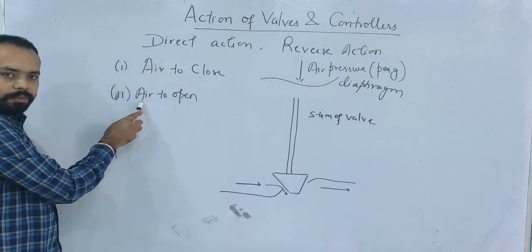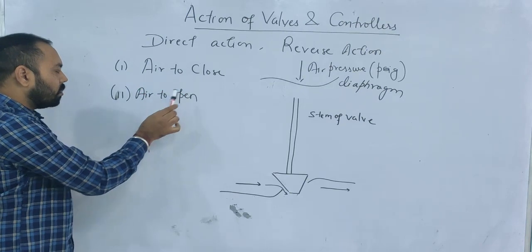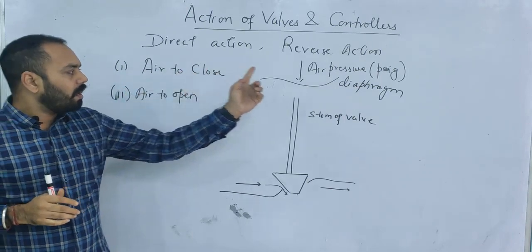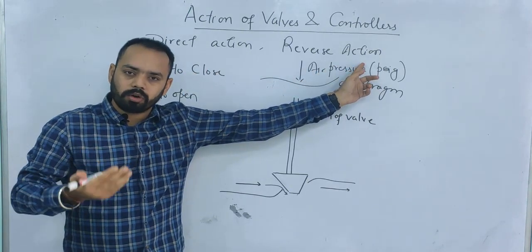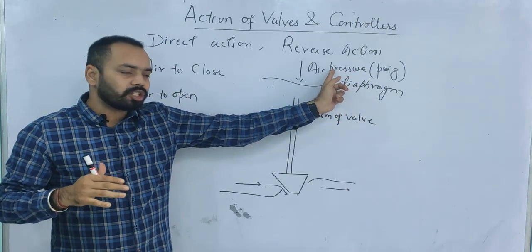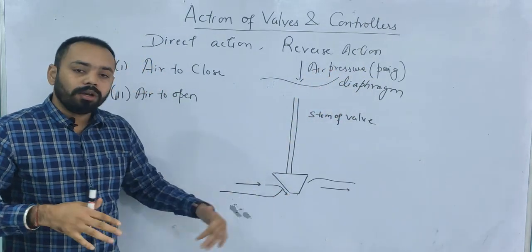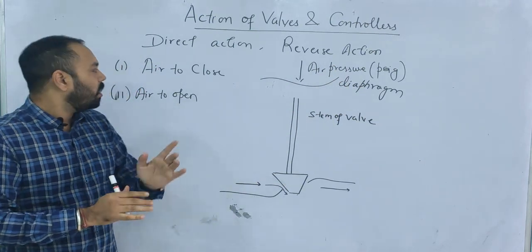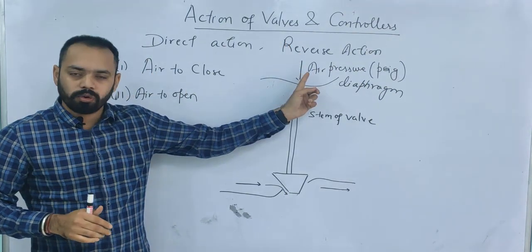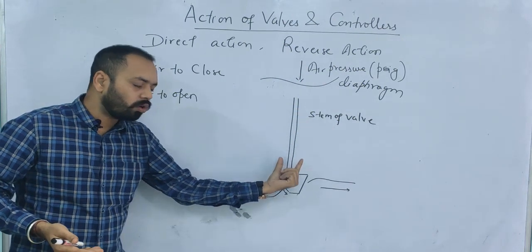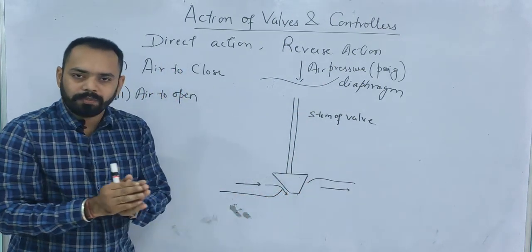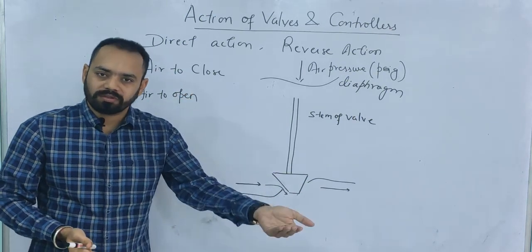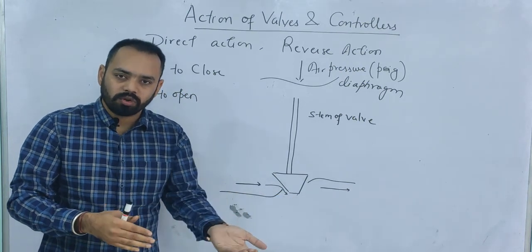What does 'air' mean here? Air stands for the air pressure coming to the valve from the controller. The controller output is converted into the corresponding air pressure and it serves as the input of the valve. Air-to-close means: as the pressure coming from the controller to the valve increases, the valve will be closed. As the air pressure increases, the stem shifts downwards, the opening decreases, and the flow decreases.